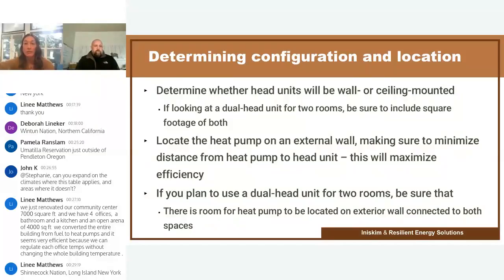You don't want to mount these directly above a window for a lot of reasons. It's going to get in the way of the condensate line that needs to run down and out to the heat pump. But also it's going to restrict how the air is circulating in the room if you've got it directly above a window, so you really want to avoid that if possible. If you can find an empty wall that's shaded, that's the ideal placement if you're doing the wall mounted unit. But if you don't have that, it is worth looking at those ceiling mount units.